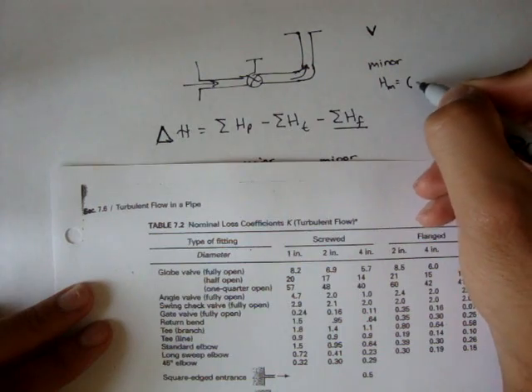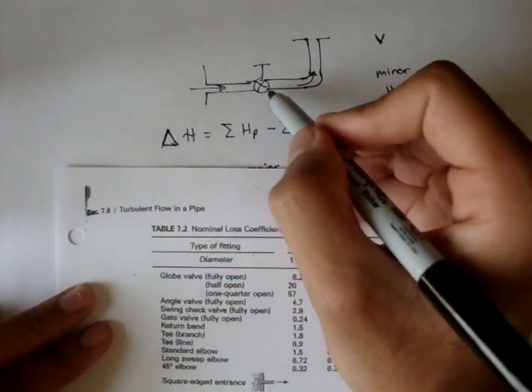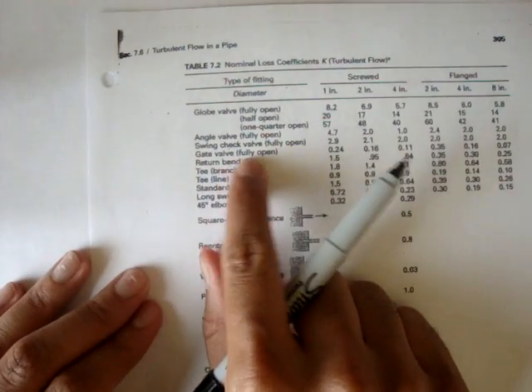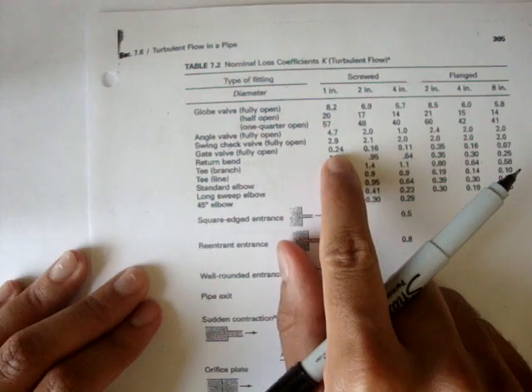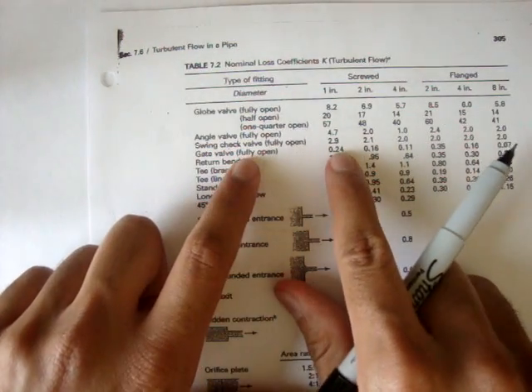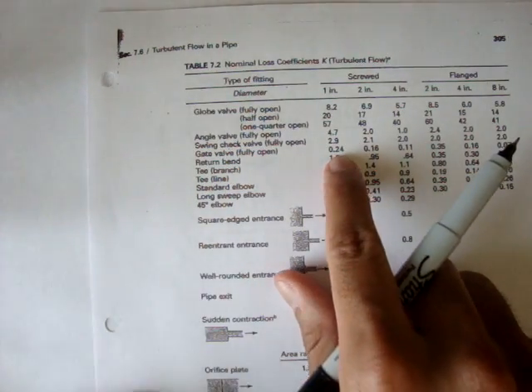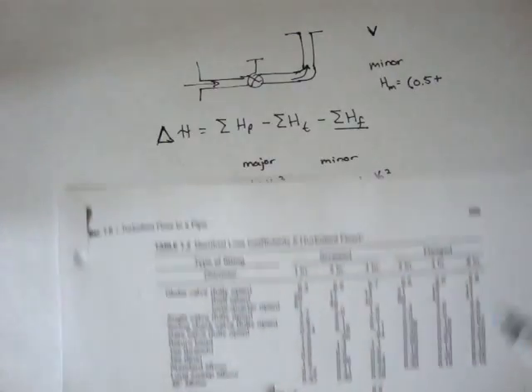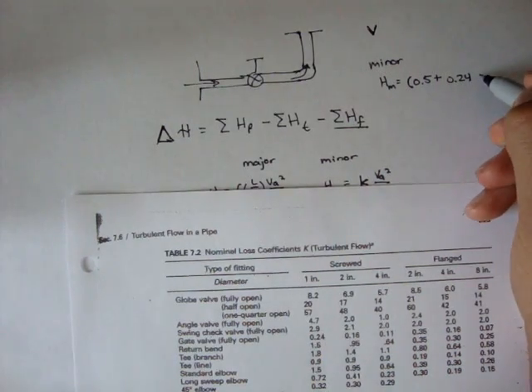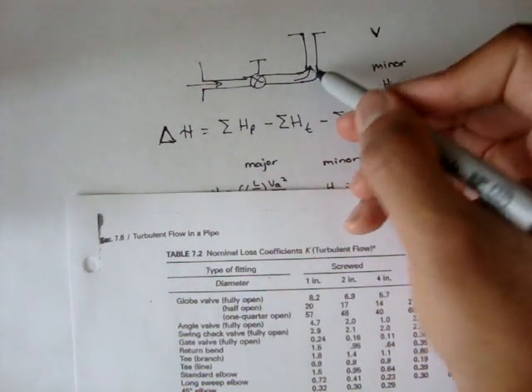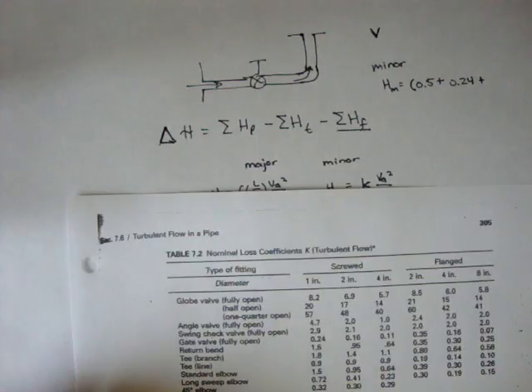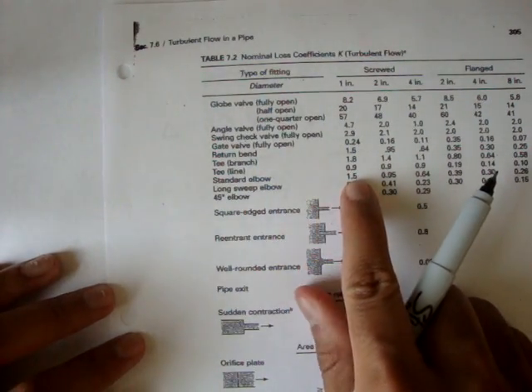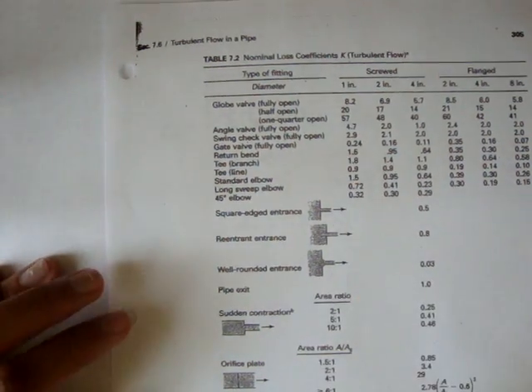So, for the entrance, it would be 0.5 plus a gate valve that's fully open, and if we look on the fully open gate valve, it's different for each diameter. Let's say it was just a 1-inch screwed gate valve that was fully open. The K value would be 0.24, 0.24 plus the standard threaded elbow. And again, let's just say it's a 1-inch diameter screwed standard elbow. Well, the K for that is 1.5.